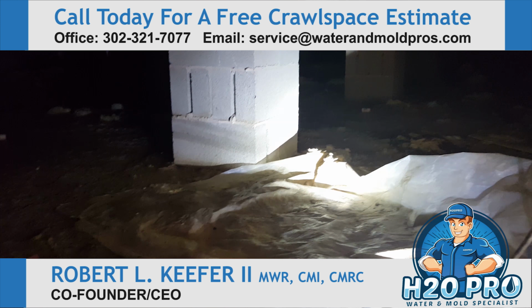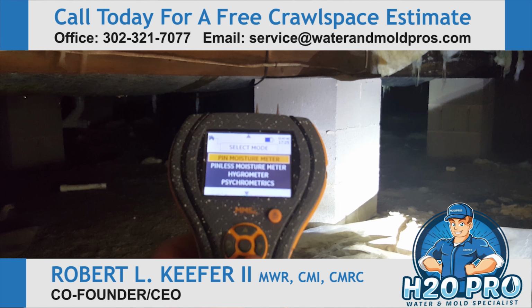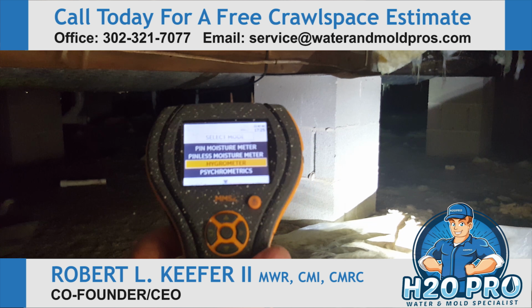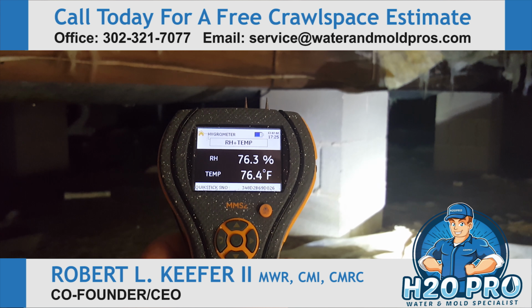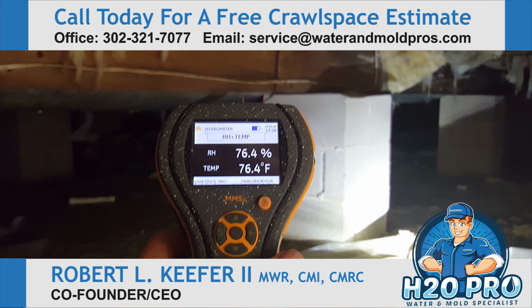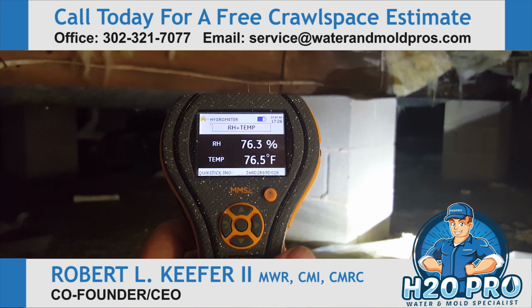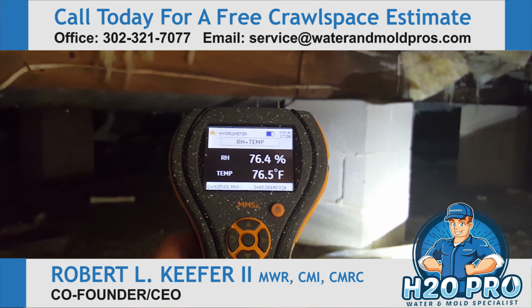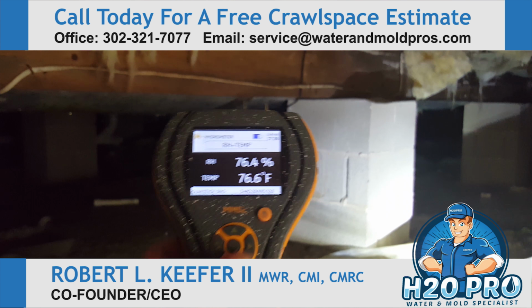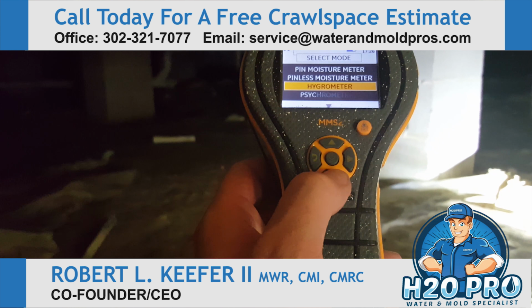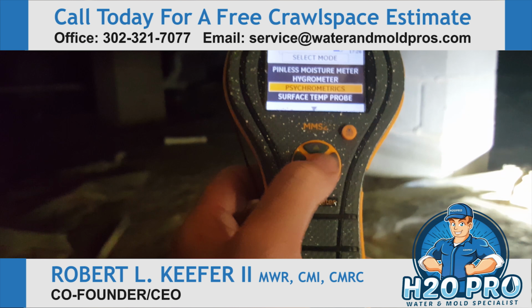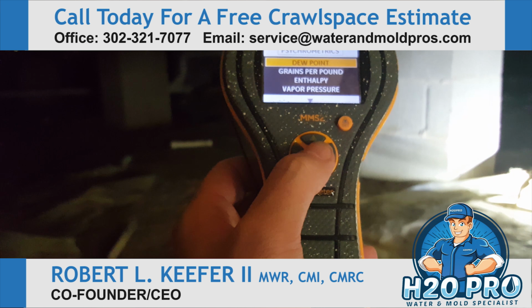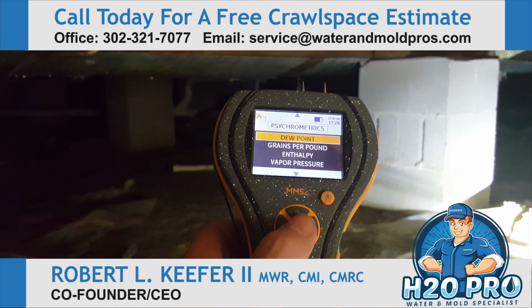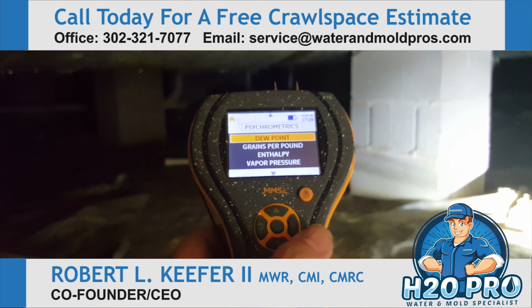The relative humidity in here is 76%. At 60% you can start having mold growth. So at 76%, you see this is a very bad crawl space, right? Now, one of the other things I want to show you is that we also can find out, is the moisture condensating on the surface? Has it reached the dew point? We simply do that.